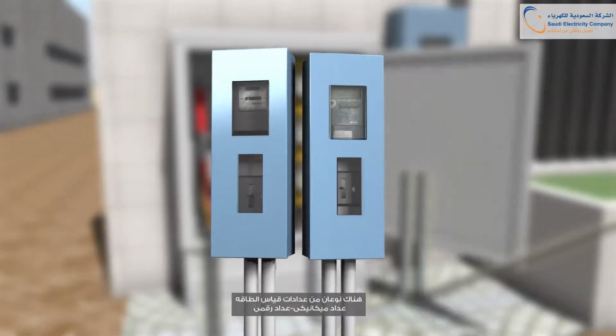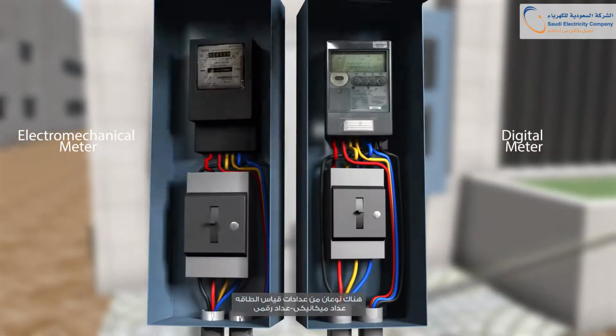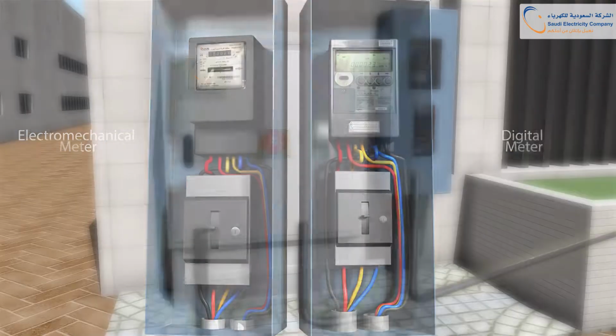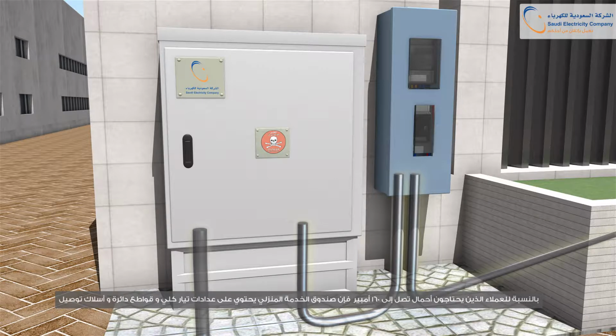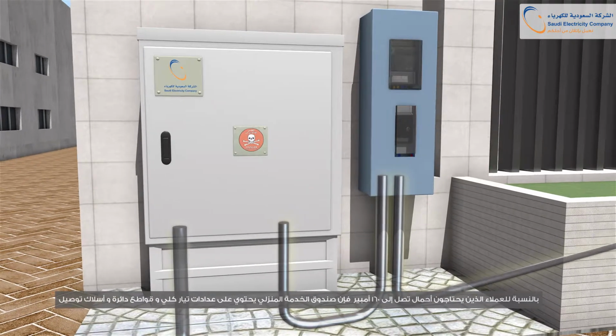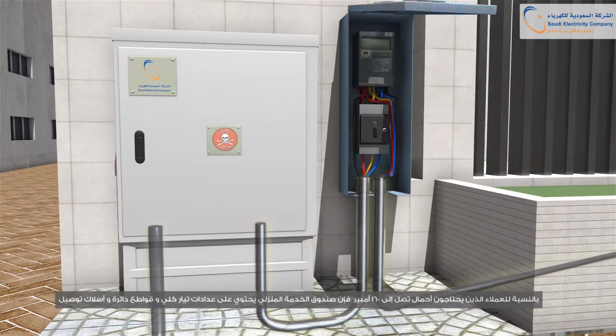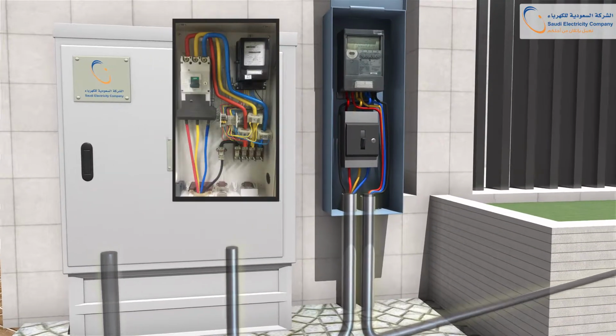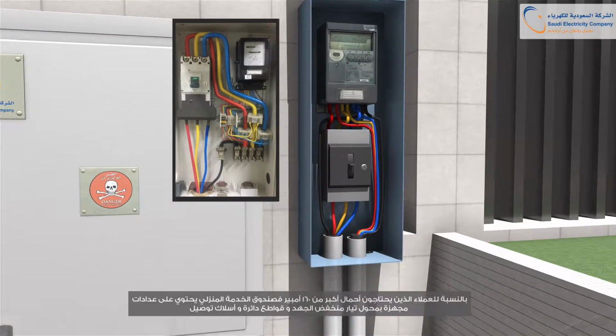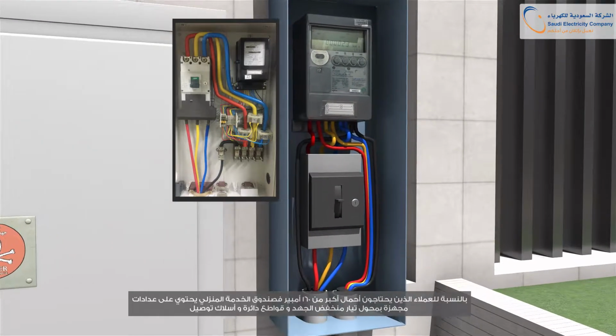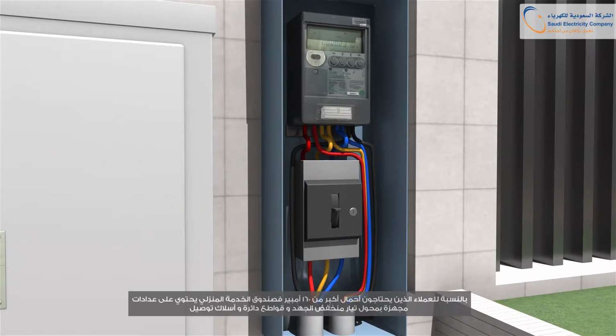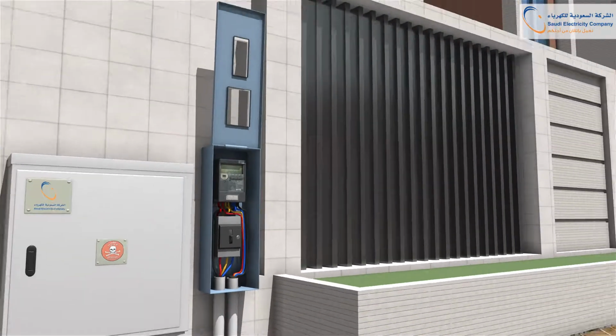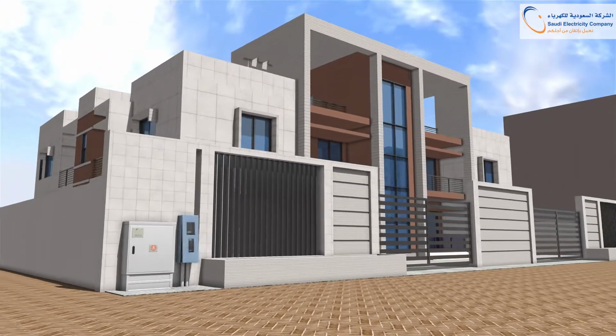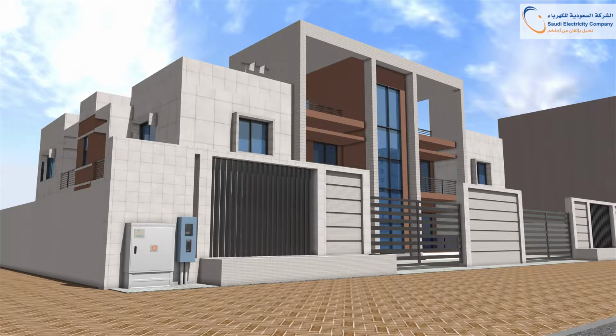There are two types of kilowatt hour meters: electromechanical meter and digital meter. For customers with loads up to 160 ampere, the house service box contains whole current meters, circuit breakers, and terminal wires. For customers with loads greater than 160 amps, the house service box contains LV current transformer meters, circuit breakers, and terminal wires.